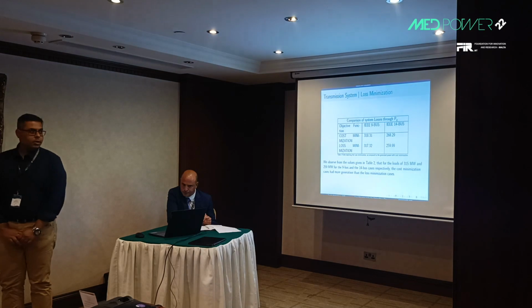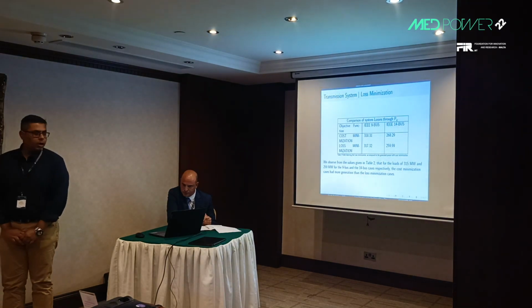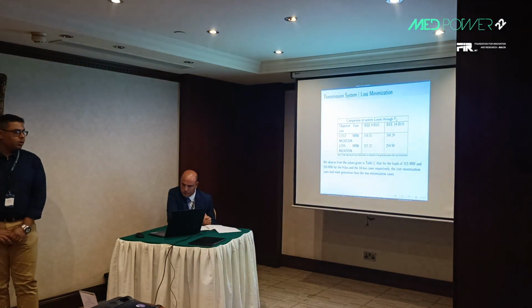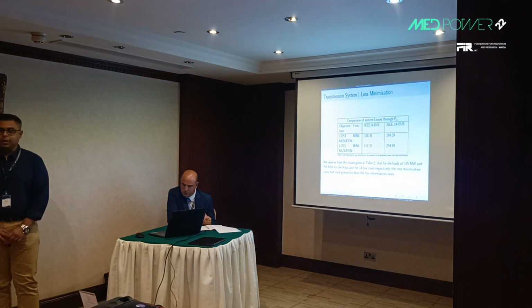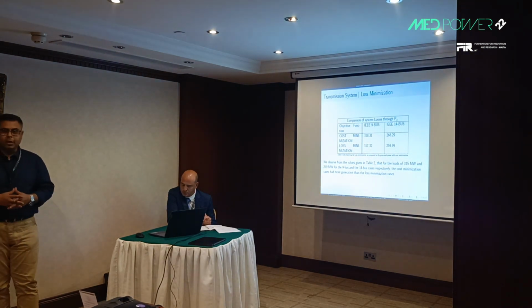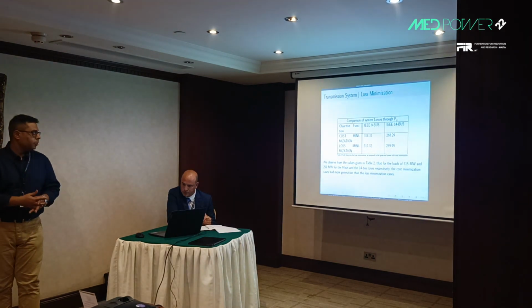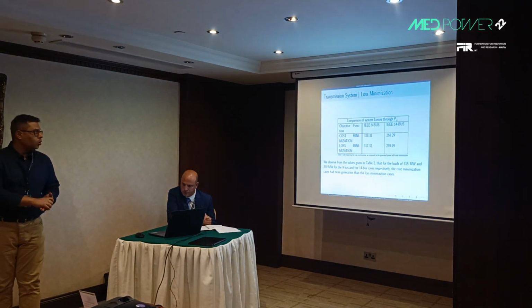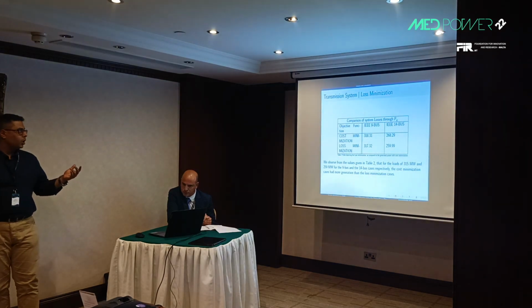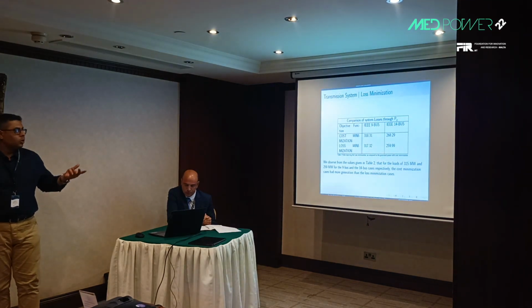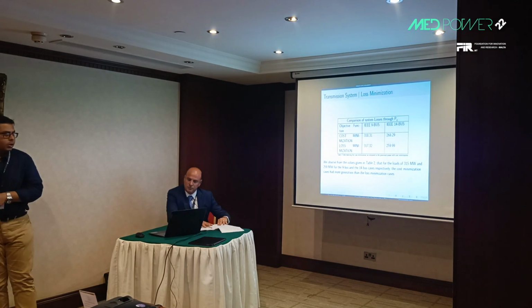Loss minimization is done with the partial relaxation technique because the partial relaxation can have loss minimization as an objective. We see that for the loads of 315 megawatt and 259 megawatt, we have somehow reduced the losses with the help of the partial relaxation technique.